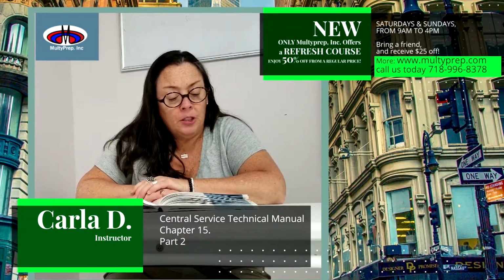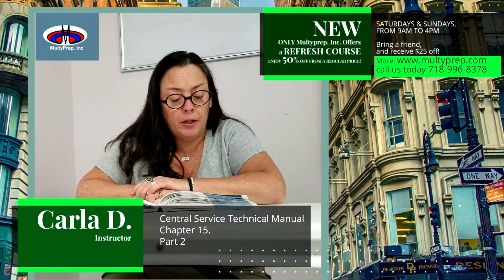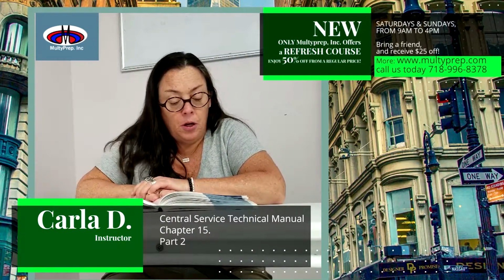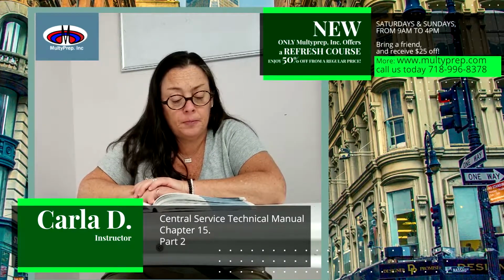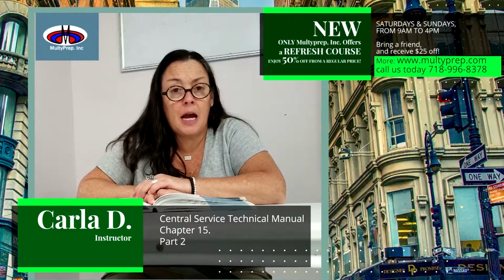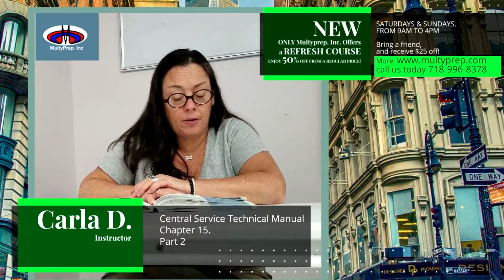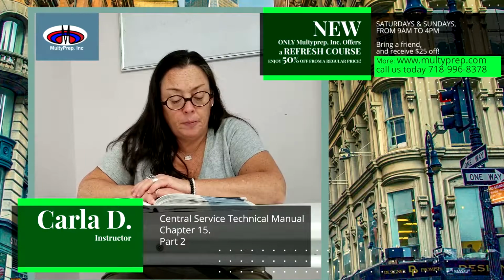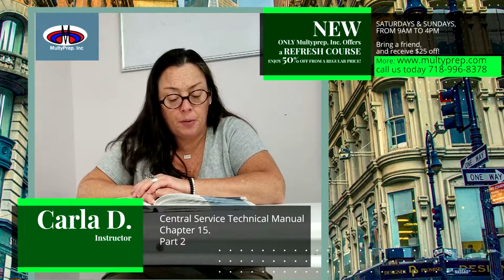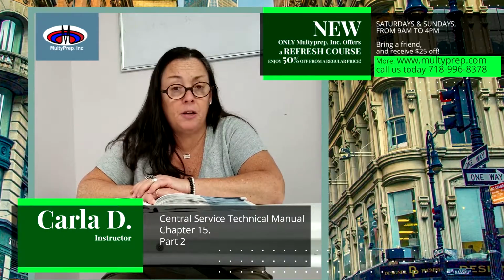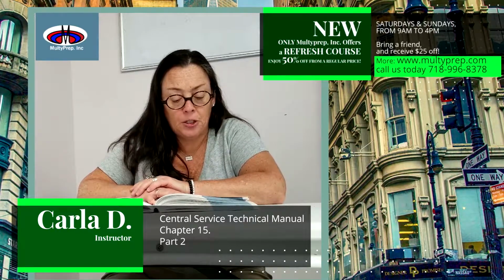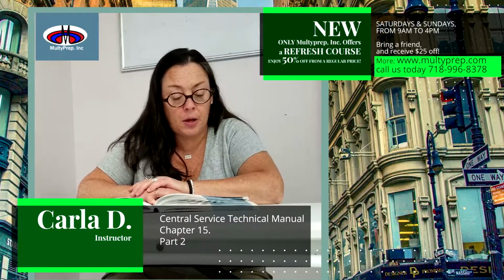Hydrogen peroxide systems. Several types of low temperature systems use hydrogen peroxide as a sterilant. While the systems operate similarly, there are some key differences in the types of systems. Hydrogen peroxide gas plasma. Background. The more recent low temperature sterilization technologies cleared by the FDA are considered oxidative processes. This includes hydrogen peroxide gas plasma.